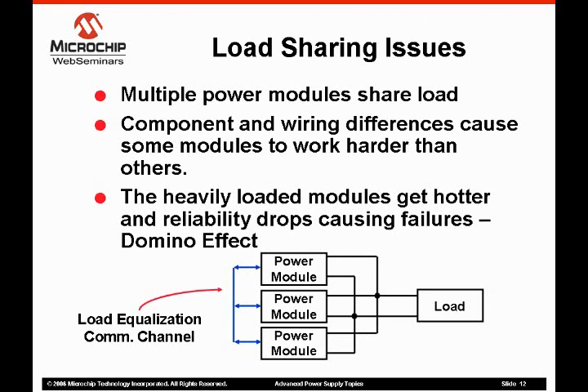If a power supply module fails, the remaining modules continue supplying power to the system. The user can remove failed modules and install replacements without powering down the system. Load sharing is often a requirement for large computer system power supplies where fault tolerance and high system reliability is a necessity.